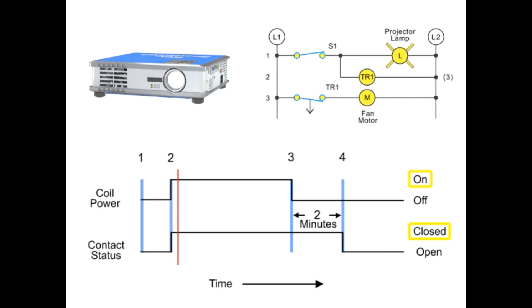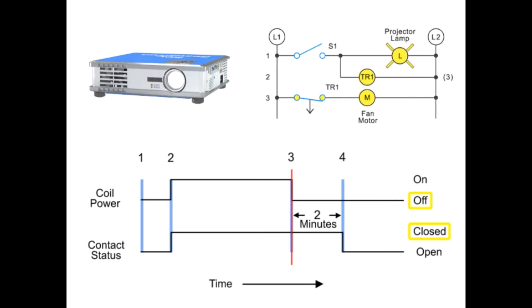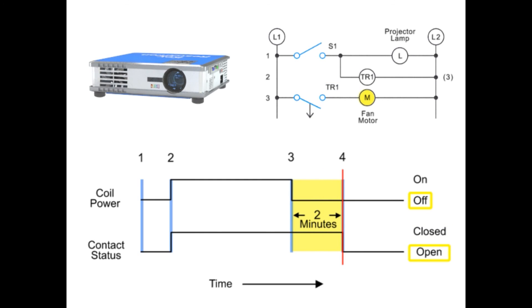The projector bulb and the cooling fan remain on as long as switch S1 stays closed. When switch S1 is opened, the projector bulb turns off and power is removed from the timer. Contacts TR1 remain closed for a preset period of time and then open, causing the cooling fan to turn off. This off-delay timed open circuit is generally set to adequately cool the projector equipment before it shuts off.